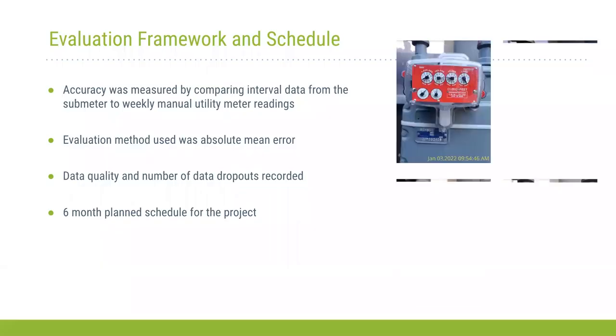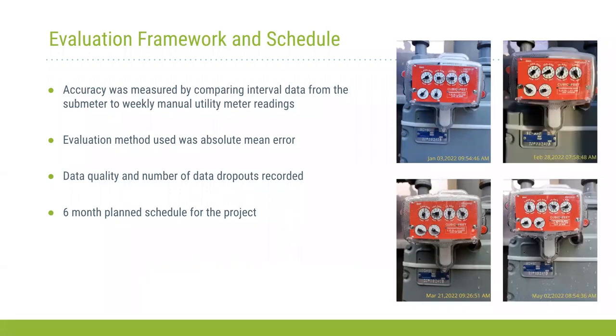As far as the evaluation framework and schedule, we planned this evaluation to be a 6-month period, and I'll explain why we don't have a full 6 months of data. The accuracy was measured by comparing interval data to manual meter reads. Someone at the facility went to the meter at specific times and took photos of it, which you can see on the right, with timestamps on each photo. We recorded all that data and compared it to the new interval data from the vendor's submeter sensor option. The evaluation method used for measuring accuracy was the absolute mean error, and data quality and number of dropouts were also recorded in this assessment.